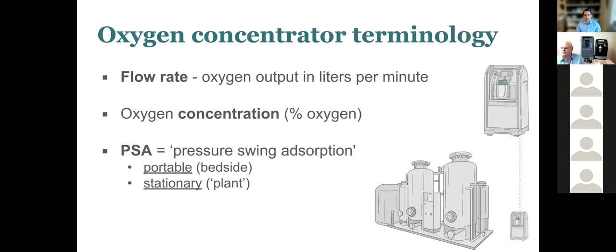In terms of terminology, just a couple of things to get out of the way. When we're talking about flow rate, we're talking about the oxygen coming out of the concentrator in liters per minute. What's coming out, we'll talk about the concentration of oxygen, or the percent of oxygen that the concentrator is generating. And then finally, we may use the word PSA, or pressure swing adsorption. This refers to the general way in which these devices operate.